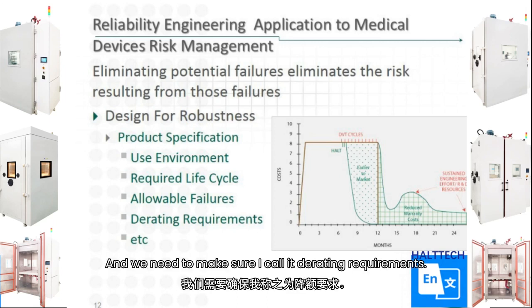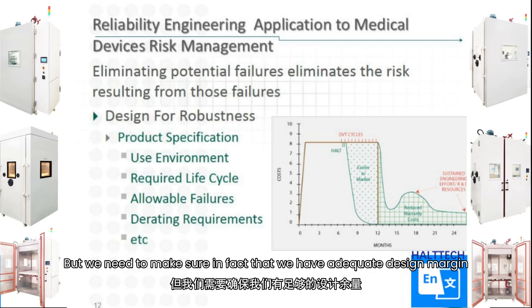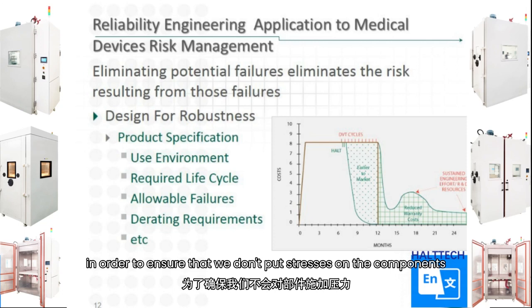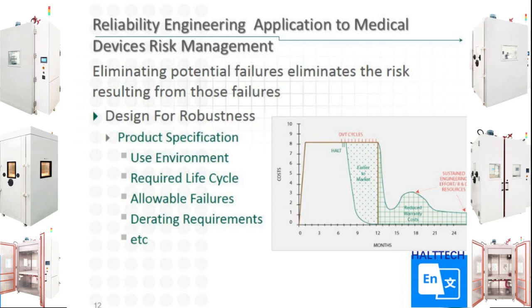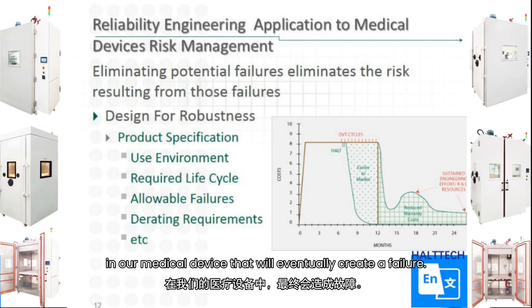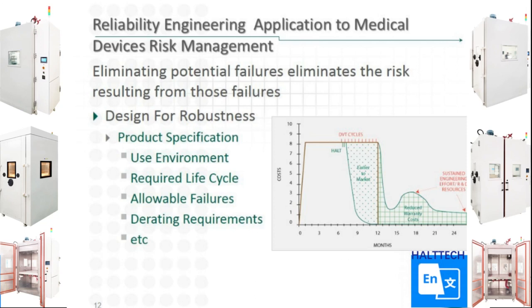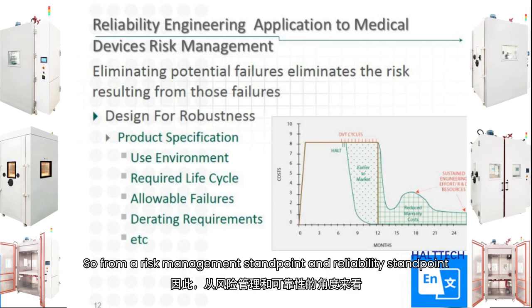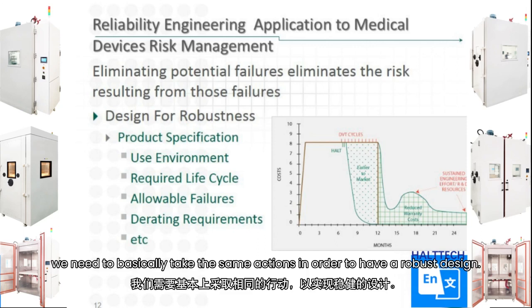And we need to make sure, I call it derating requirements, but we need to make sure, in fact, that we have adequate design margin in order to ensure that we don't put stresses on the components in our medical device that will eventually create a failure. So from a risk management standpoint and a reliability standpoint, we need to basically take the same actions in order to have a robust design.